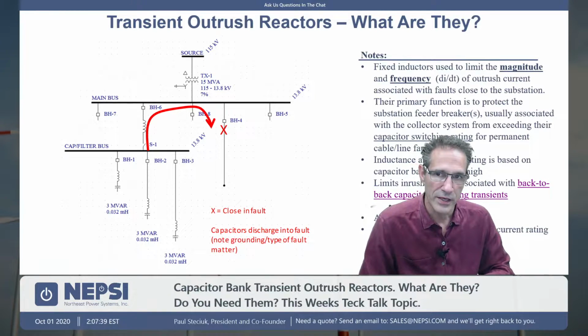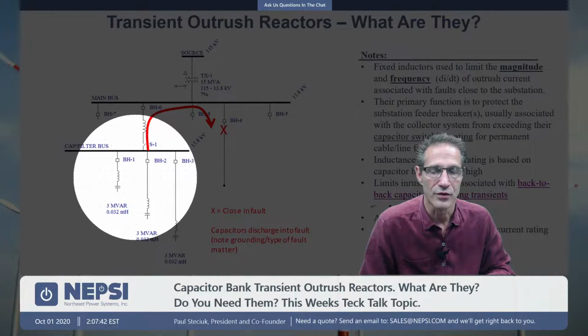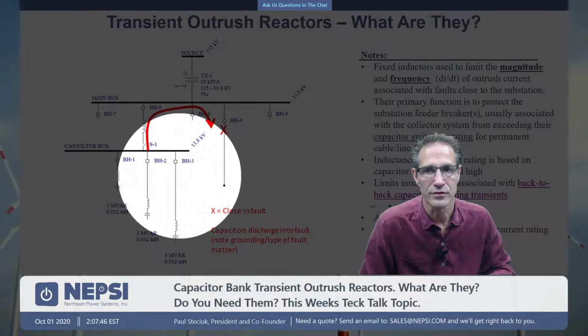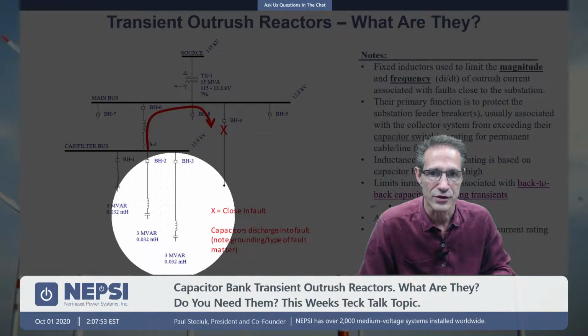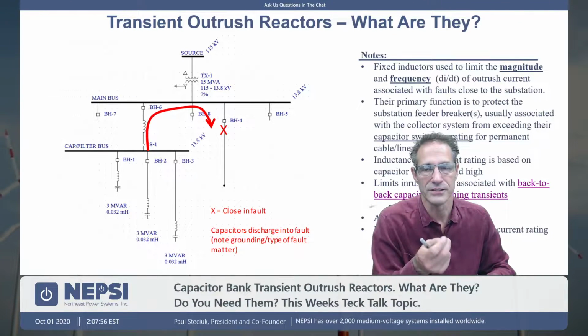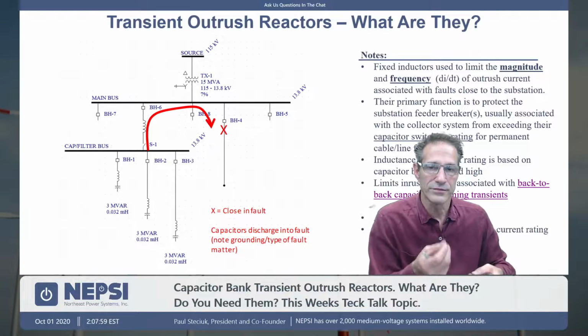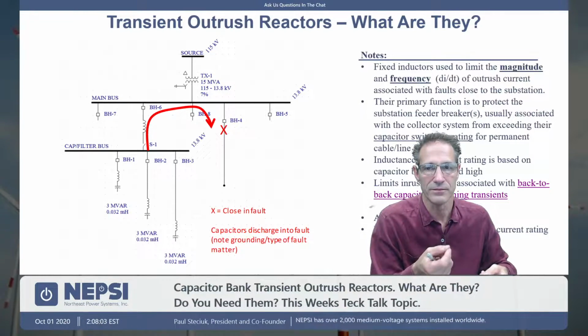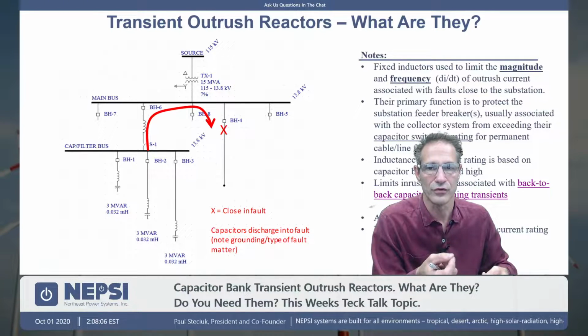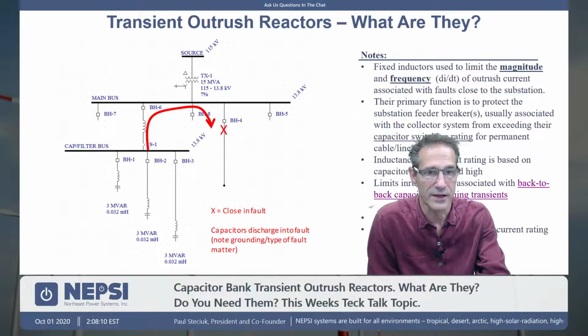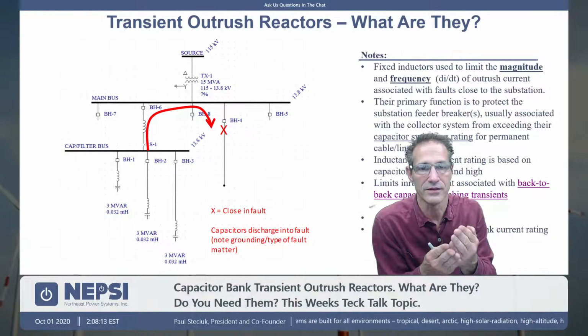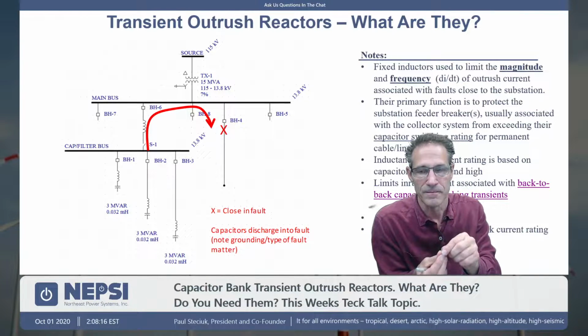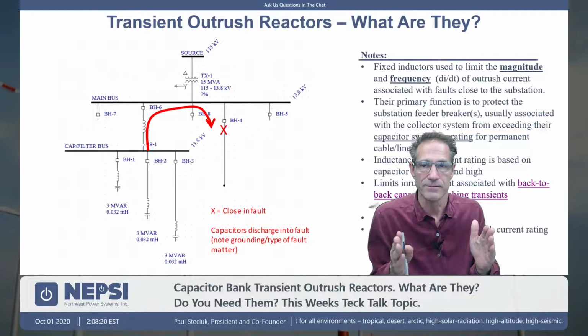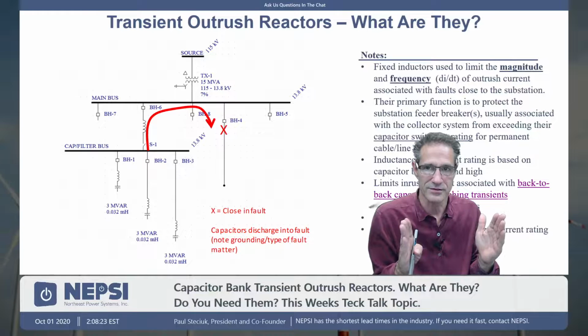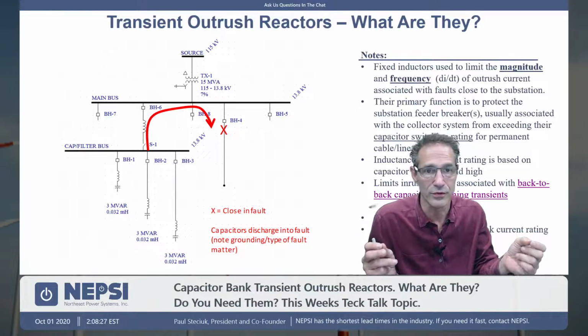So if we had a situation where BH-1 and BH-2 were closed, and we were looking to close BH-3, the charge current within these two capacitor banks would discharge into that third bank, and that breaker or switching device, BH-3, will be subjected to a very high di/dt, a very high peak current, with high magnitude and high frequency. And if you think about it, as the contacts close, this very high di/dt would have a tendency to want to weld the contacts closed. So in a metal enclosed cap bank, and even open air banks, the only impedance between one stage and the next is the impedance of the bus work or of the cabling.